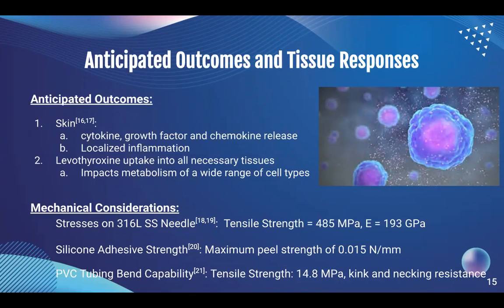Silicone adhesive is shown to be one of the strongest medical adhesives. The silicone adhesive on the infusion site will not release from simple brushing of clothing or bumping a surface. Silicone adhesive will also remain strongly bonded in the presence of water and requires a harsher solvent such as isopropanol to remove. The PVC tubing for levothyroxine delivery has high kink and necking resistance. The tube will remain optimal for flow of the drug from the pump to the infusion site and will not kink or break during everyday typical actions.